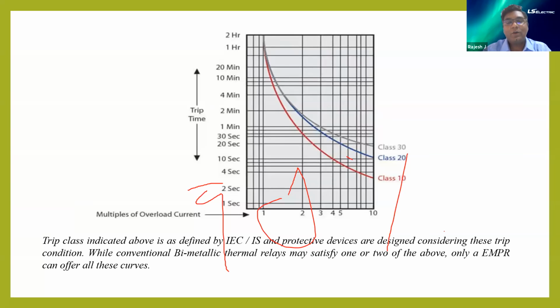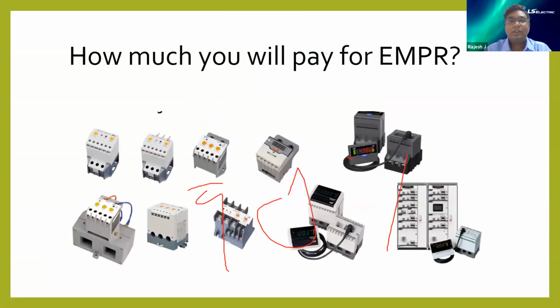So there is one product called the electronic motor protection relay, which will take care of all the classes, class 5, class 10A, class 20, class 30. This device will take care of all the tripping characteristics. For example, we all know an overload relay costs around 1,000 rupees. For the electronic motor protection relay, the EMPR, how much would you pay as a user? You can just type in the chat box.